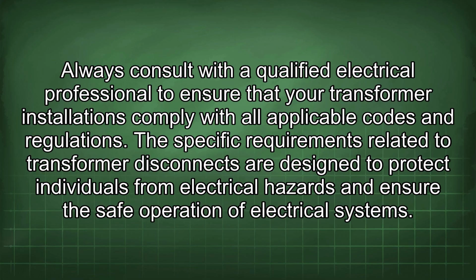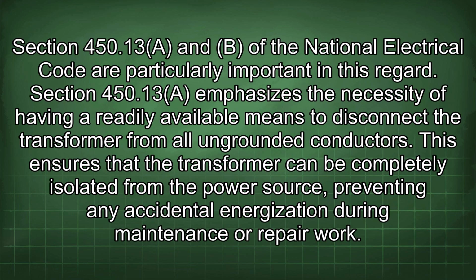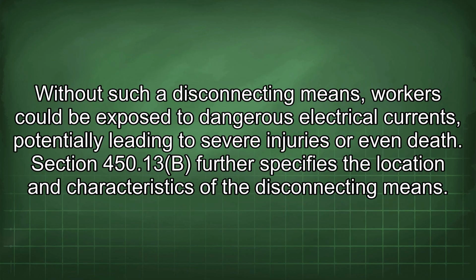The specific requirements related to transformer disconnects are designed to protect individuals from electrical hazards and ensure the safe operation of electrical systems. Section 450.13 A and B of the National Electrical Code are particularly important in this regard. Section 450.13 emphasizes the necessity of having a readily available means to disconnect the transformer from all ungrounded conductors. This ensures that the transformer can be completely isolated from the power source, preventing any accidental energization during maintenance or repair work. Without such a disconnecting means, workers could be exposed to dangerous electrical currents, potentially leading to severe injuries or even death.